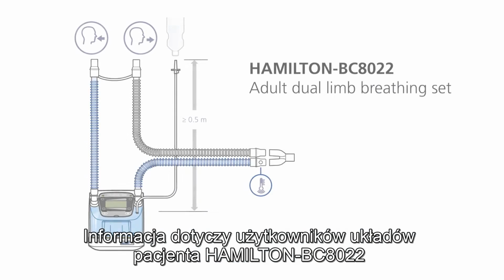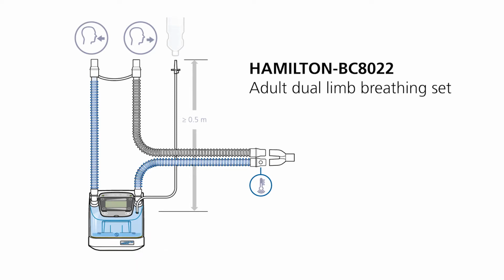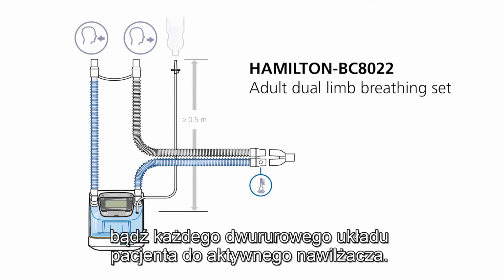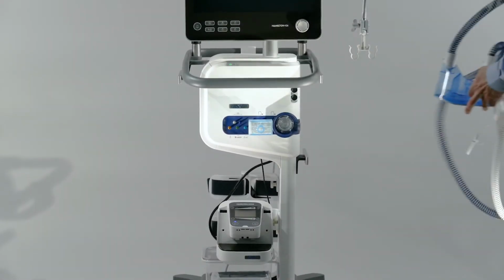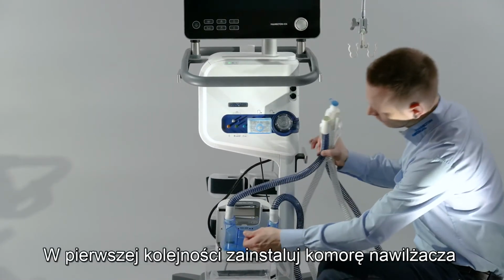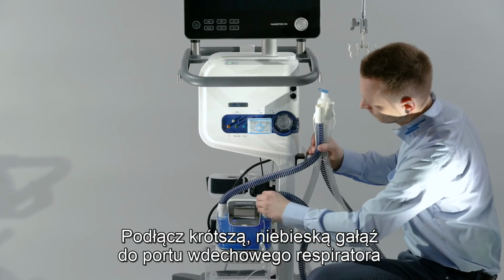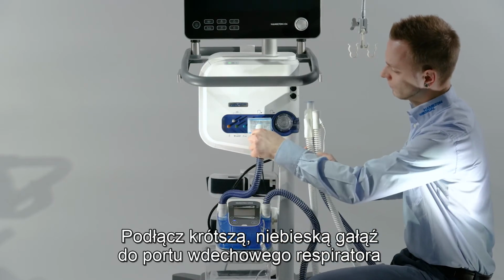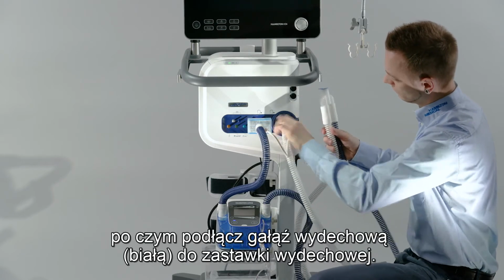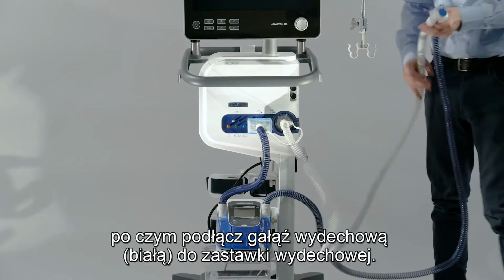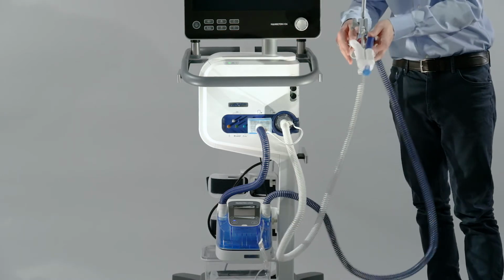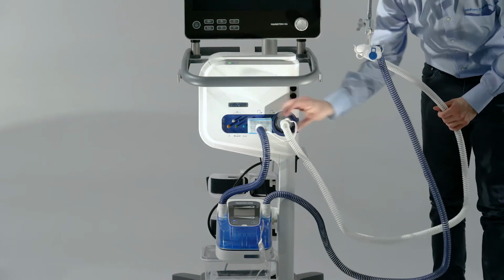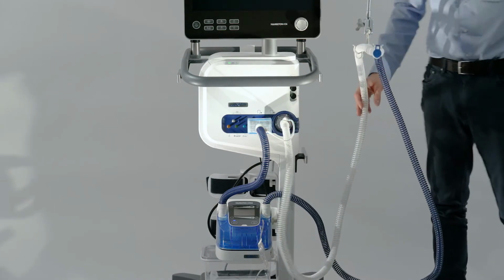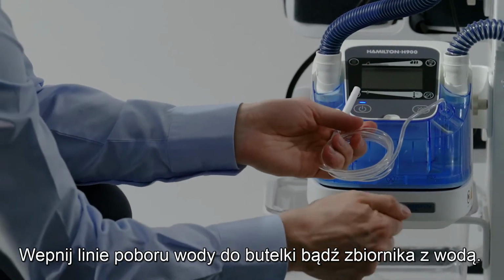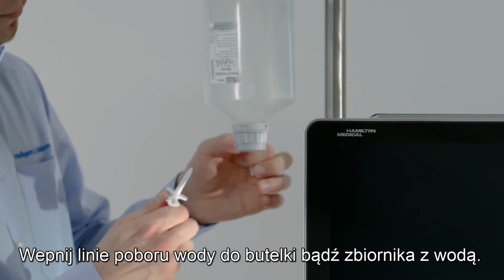The following information applies if you are using the Hamilton BC 8022 breathing circuit or any other double-limb breathing circuit for an active humidifier. First, insert the humidifier chamber. Connect the shorter blue tube to the inspiratory port on the ventilator, and then connect the expiratory tube to the expiratory valve. Insert the water feed line into the water bag or bottle.